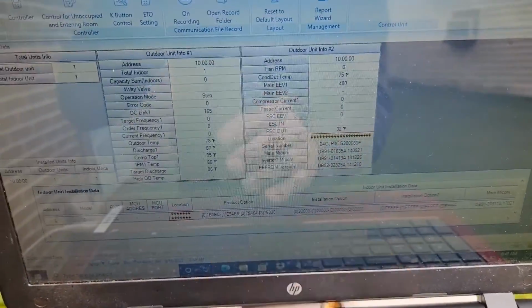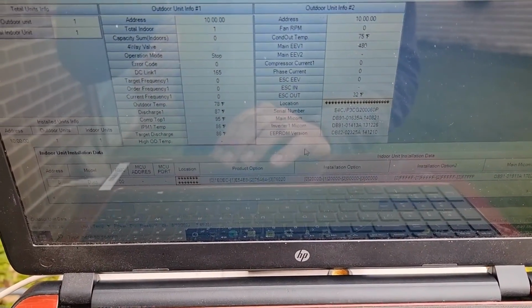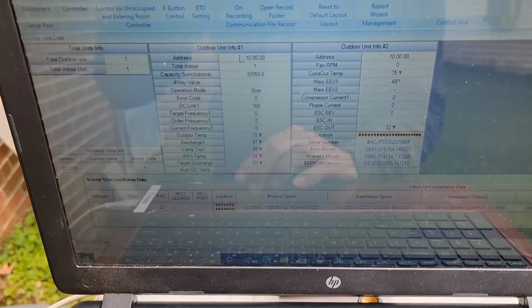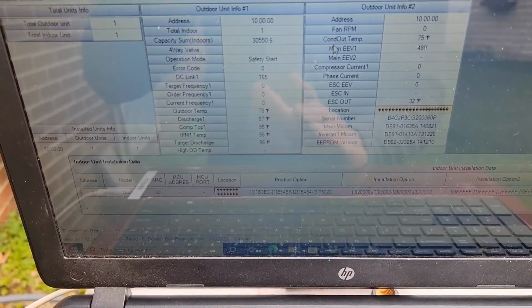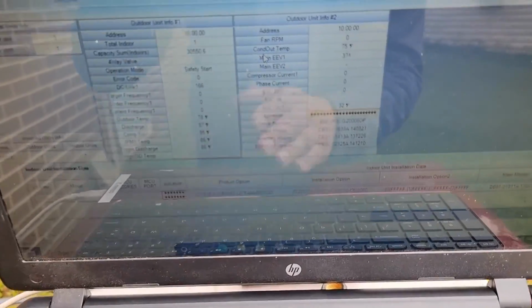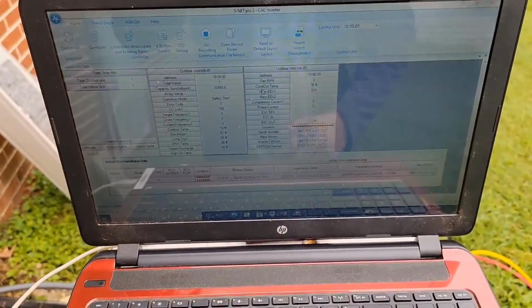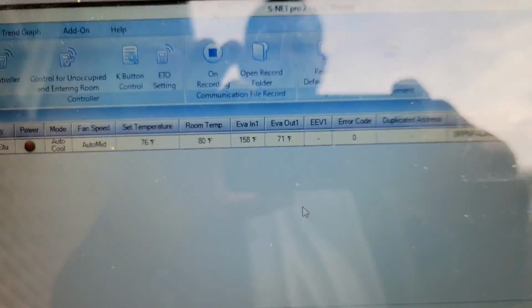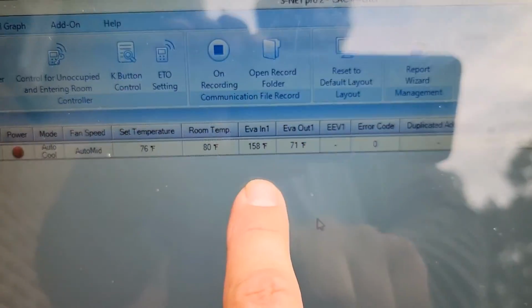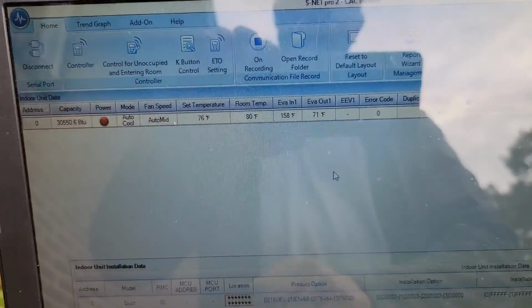Went in and hit connect, and now I can measure. I can look at some of these temperatures, try to see if anything's off. What I'll do is I'll look at the sensors, try to see what they're reading as far as the indoor sensors, outdoor sensors. I'll look at my EEV valve, want to make sure it's opening and closing properly because I got an E422. And because I have this software and this tool, I'm able to find the problem already.